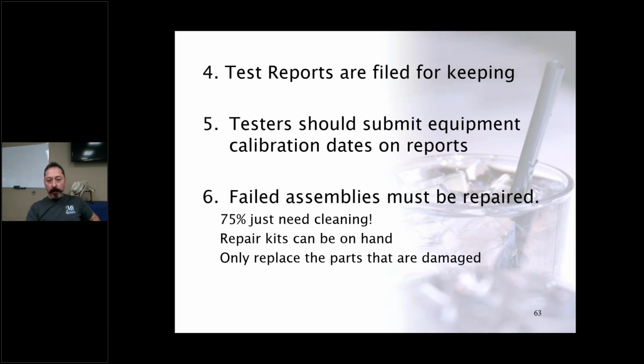So what you want to watch out for is somebody failing a backflow preventer and then suddenly just having to order all the parts there are. And those parts can get expensive. You don't always need all those parts, because we need to know what's failing. Half the time, if you take it apart, it just needs cleaning. You can reassemble it, put it all back together, and retest it to make sure it's functioning. If you take it apart to clean it, and there are damaged components in it, check valves and that sort of thing, then a repair kit can be acquired or purchased.